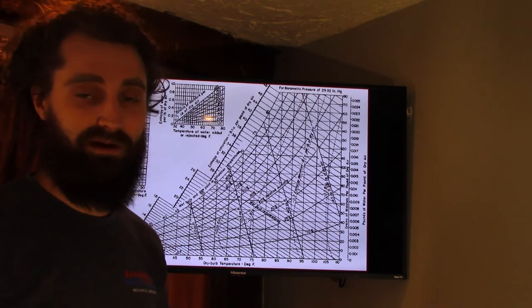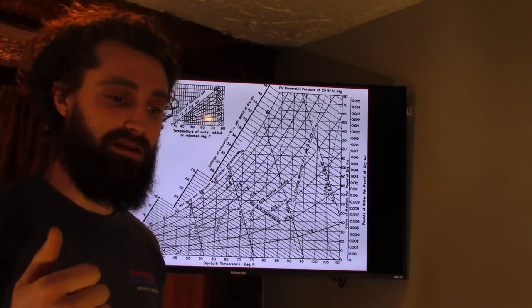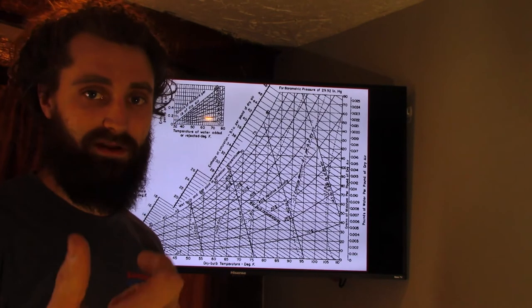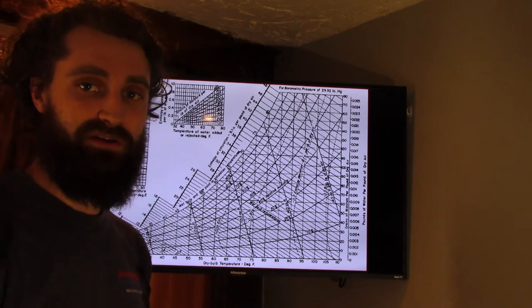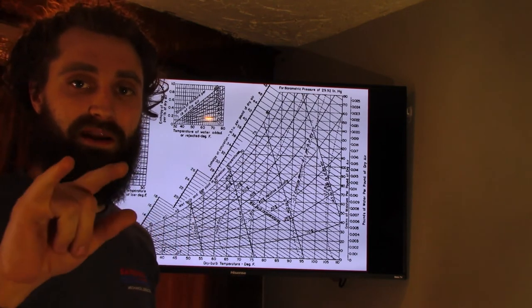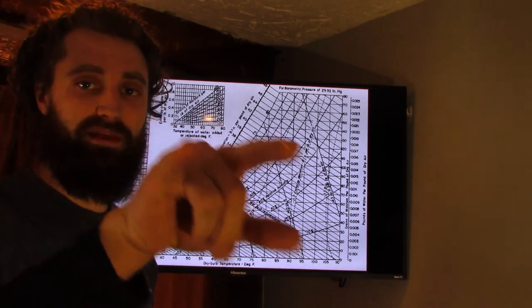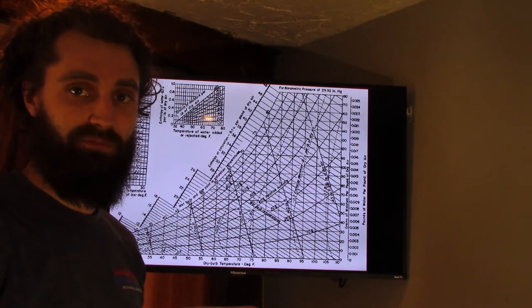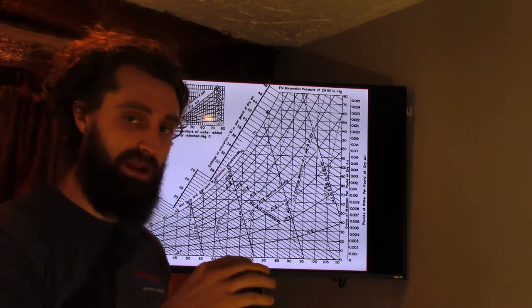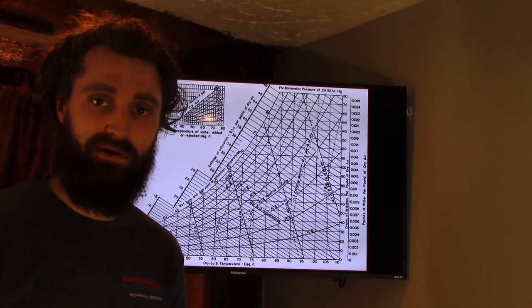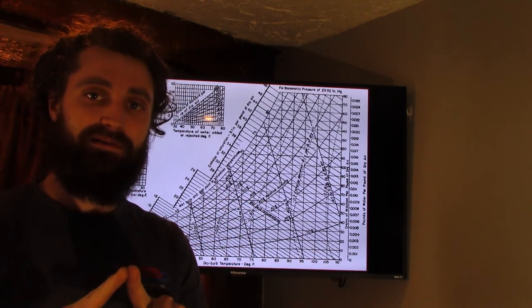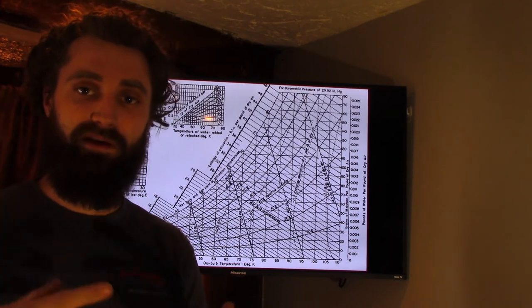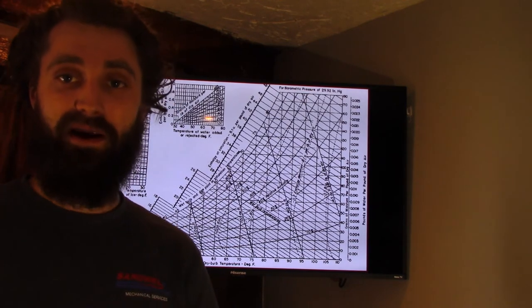And all that's just another step where we take the amperage of the condenser, the amperage of the air handler, I take the voltage of both of those, I will get a wattage of the outdoor unit as it is running, okay? I will get a wattage of the indoor unit, the blower motor, add those together, and then with that, I will divide that into a formula to figure out what the running SEER rating of that unit is.